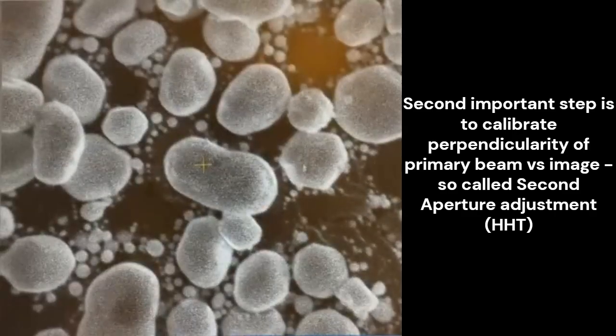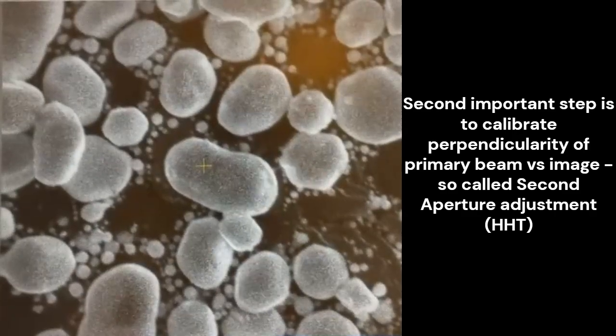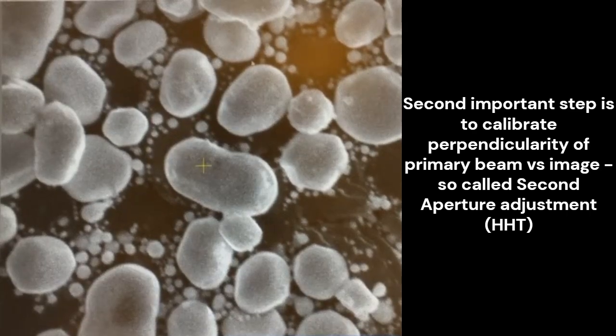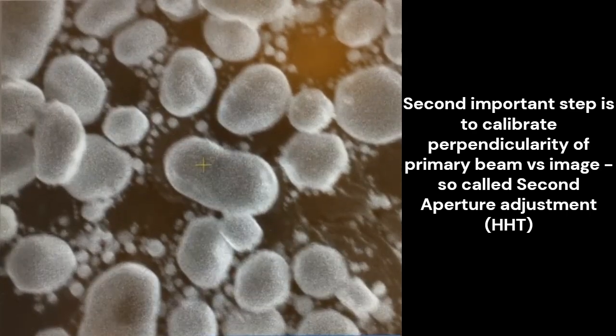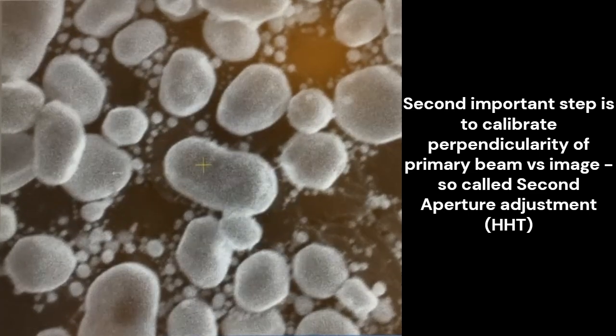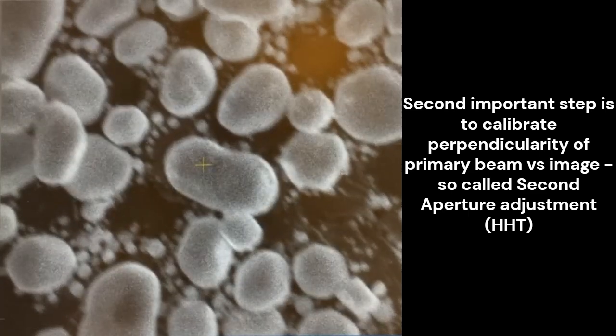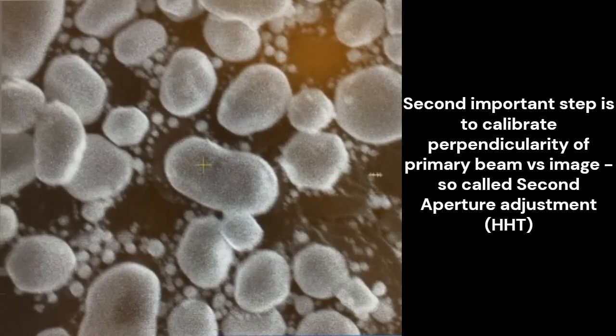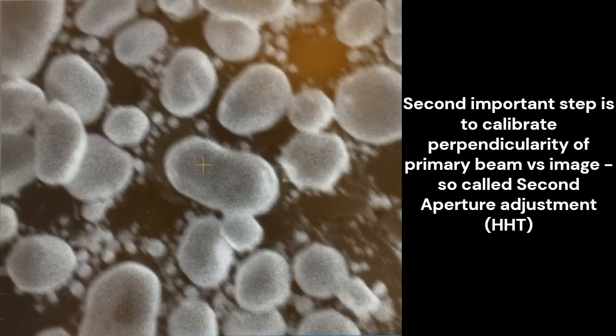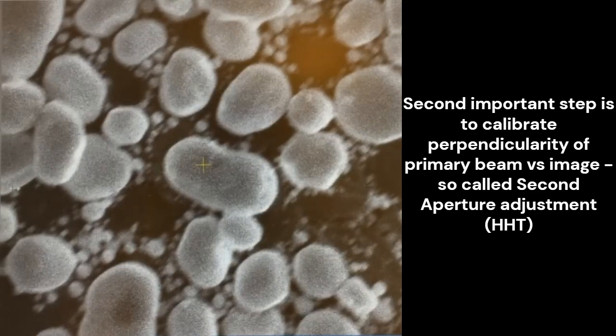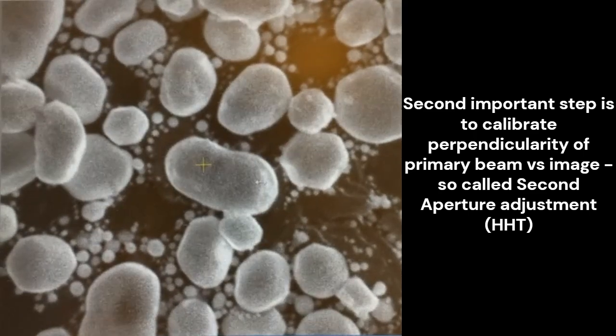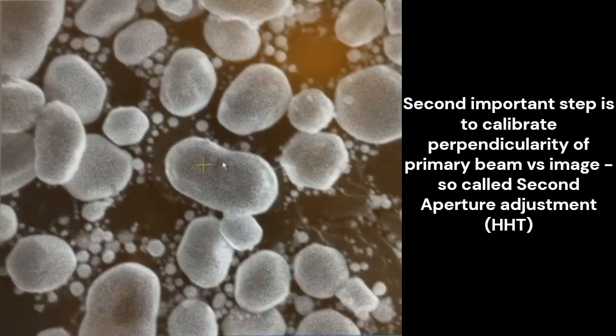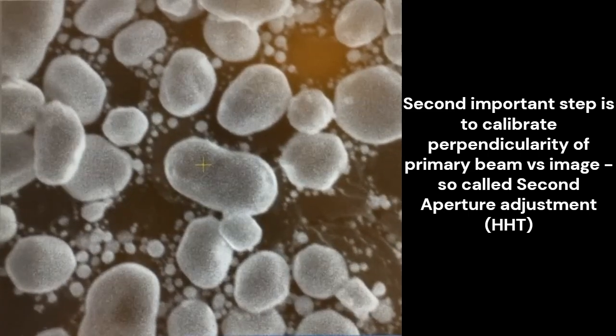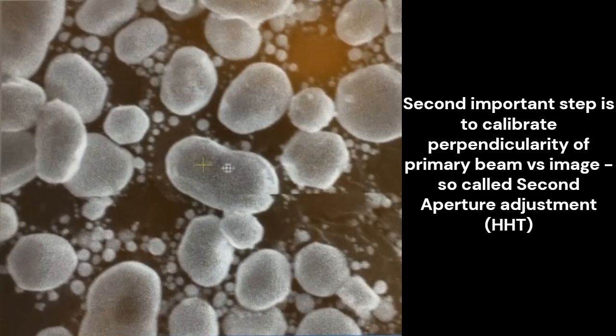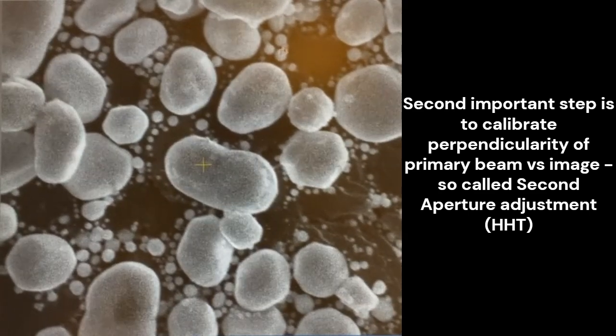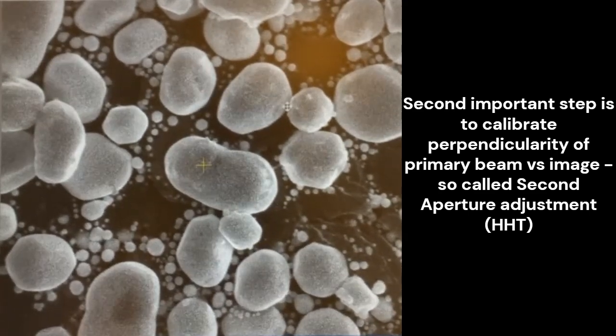What I've done though is I've induced some astigmatism by changing the lens alignment. So I want to go back and use my focus to evaluate. The image is no longer shifting, but now I can see there's some more stretching. Again, I'm going to see the stretching on one side, and diagonally stretched the other way on the other side. I'll stop somewhere in the middle where the particles are equally blurry in all directions, and then I'll change the X and Y astigmatism to sharpen up the image.